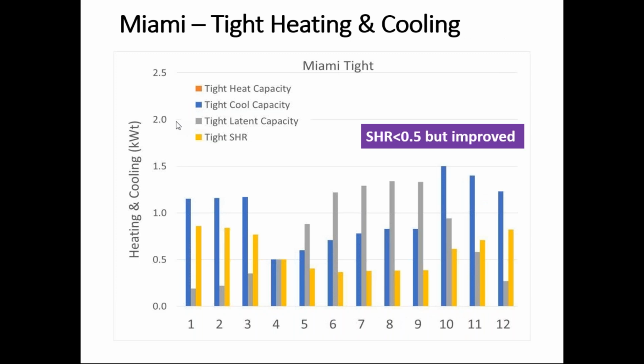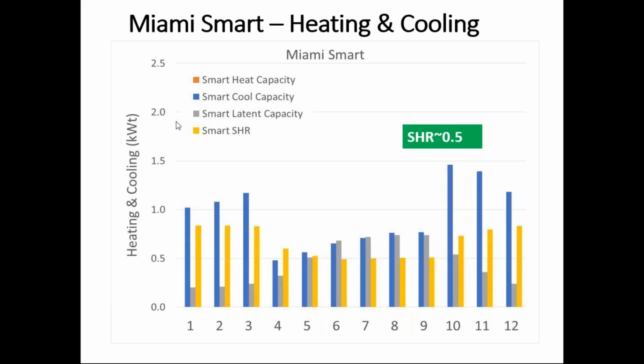As we go to contractor tight, the sensible heat ratio comes up. The latent capacity, though, is still significantly greater than the sensible cooling capacity needed. And as you smart ventilate, on average, you see that the smart ventilator will increase the sensible heat ratio up to about 1/2, where the typical air conditioning system coupled with smart ventilation, heat pump operation, and heat pump water heater operation can maybe manage on average the moisture.